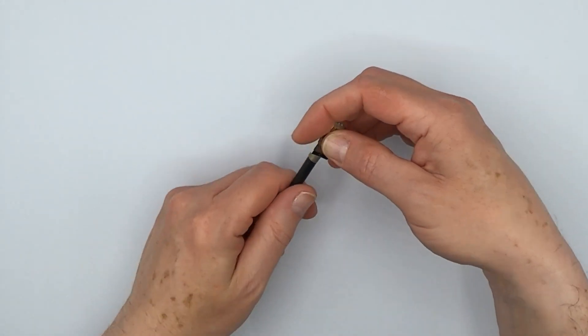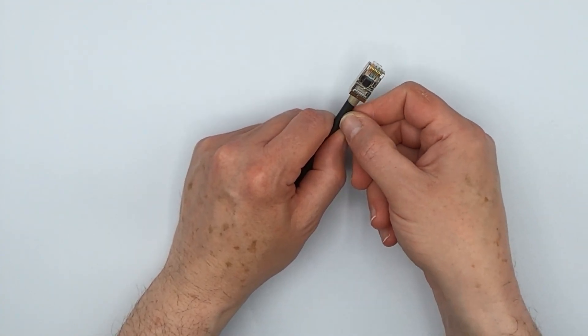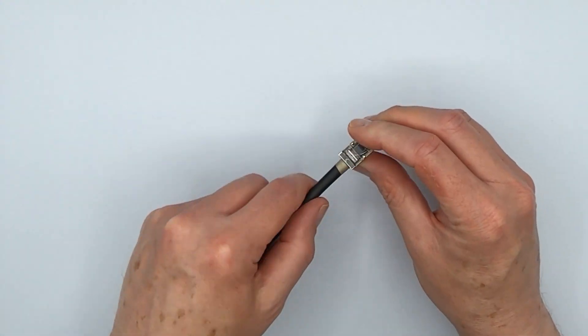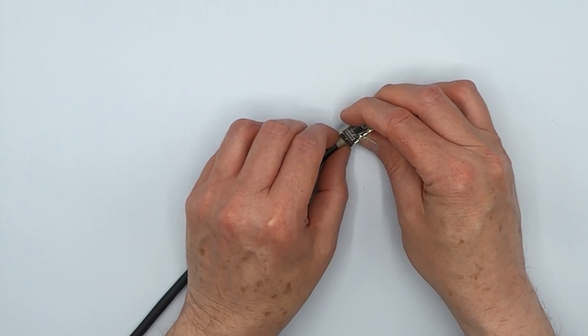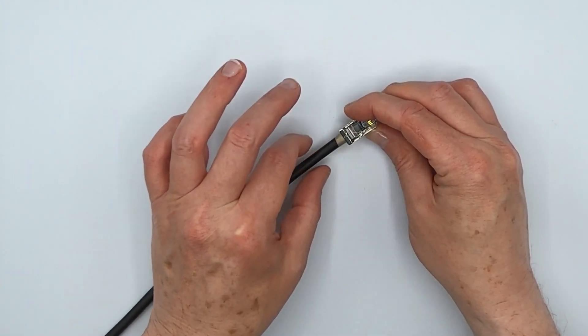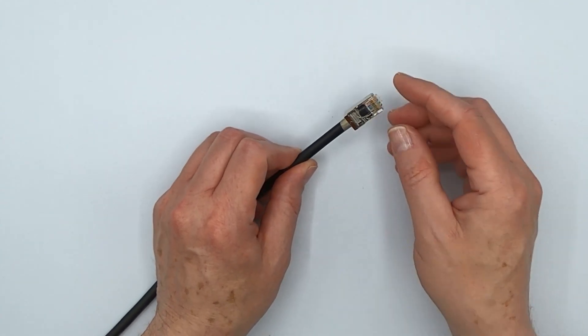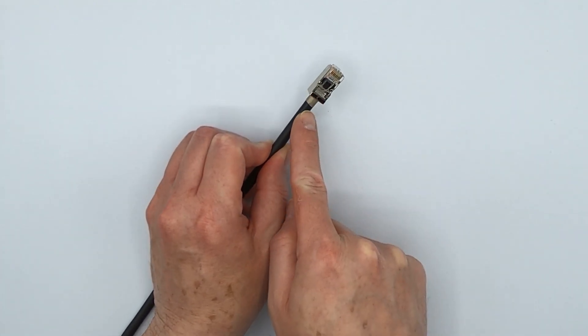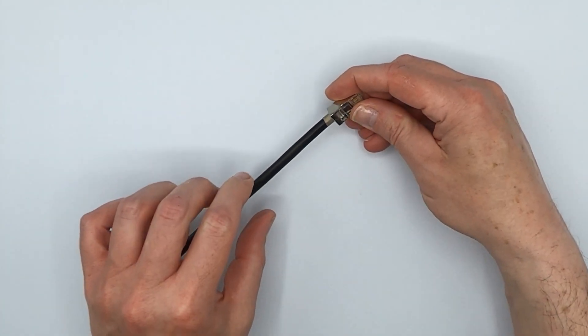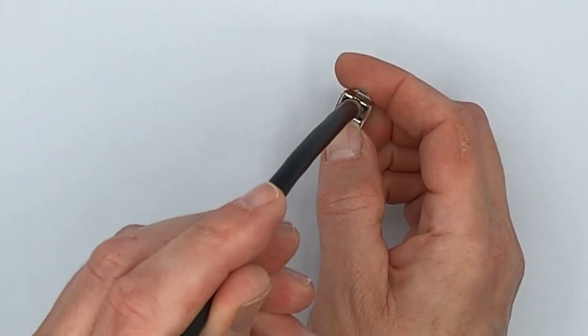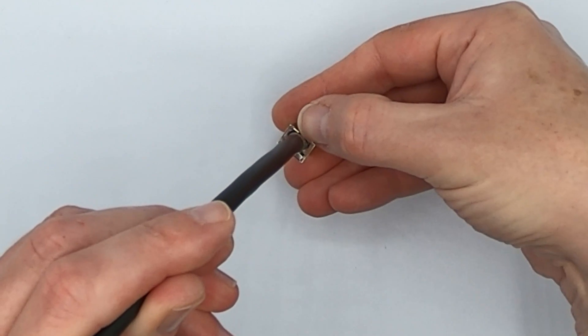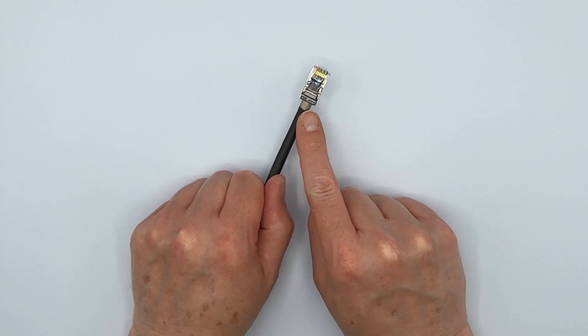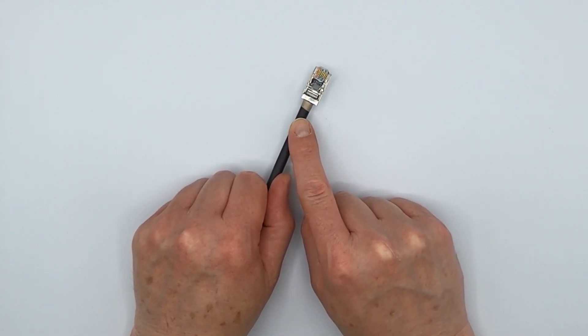And so when you are folding back a cable shield on a shielded cable, and you're pushing it into a plug that's got an internal ground, sometimes that cable shield can rip on you, or sometimes it makes it a little bit too thick to jam in there. So what you do is you skip about three-eighths of an inch back, wrap your drain wire around, put this fabric strip on there, which didn't add any thickness to that cable jacket. And then you can push it right in, and it made excellent bonding contact with the springs here inside this plug. So that's a great example of where copper fabric strips are not just a luxury, but nearly a necessity.